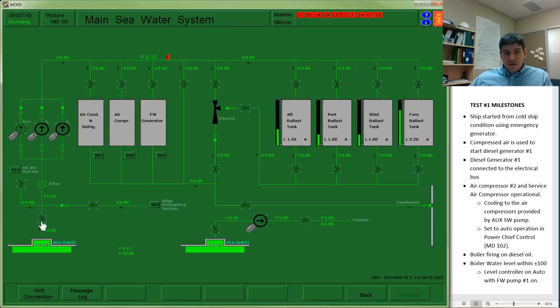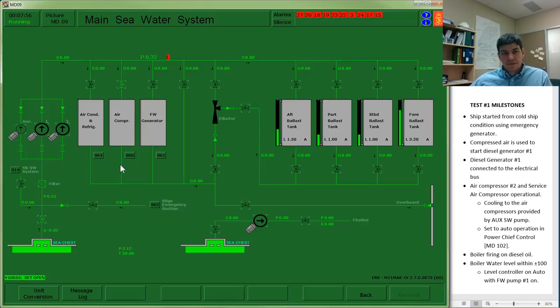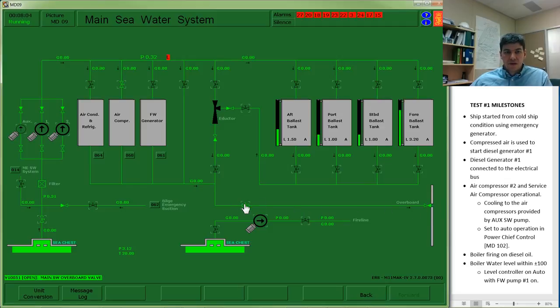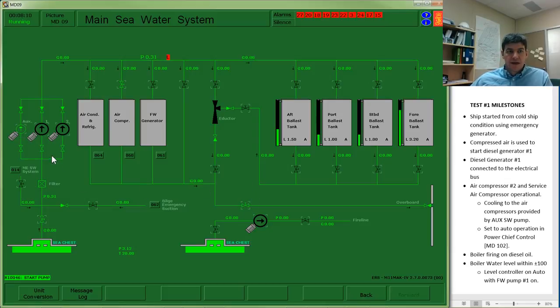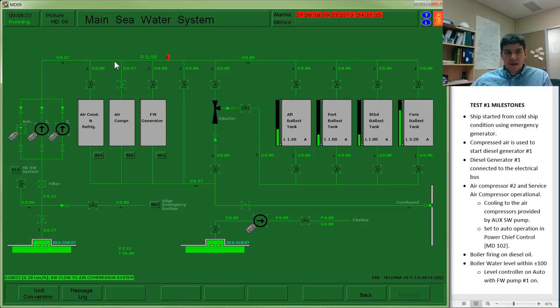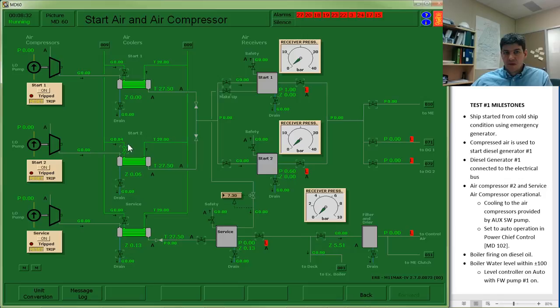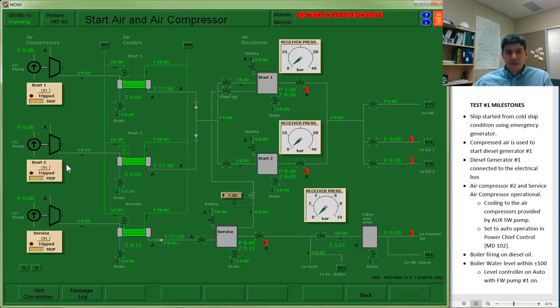I'm going to have to backtrack to page number 9 in order to try to establish flow. First thing I'll do is create my pathway starting from the sea chest through the pump's inlet valve into the air compressor system. It exits and then eventually makes its way overboard. So opening up that overboard discharge valve. Looks like my pathway is okay. So I'm going to start up my auxiliary seawater pump. You can see we're starting to get some flow, building some pressure.